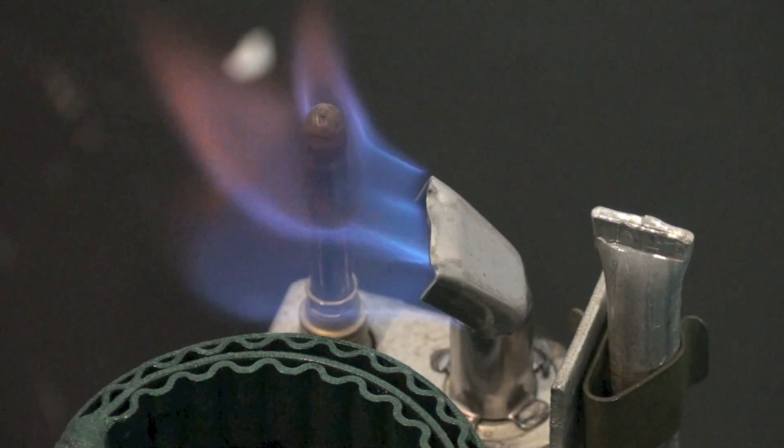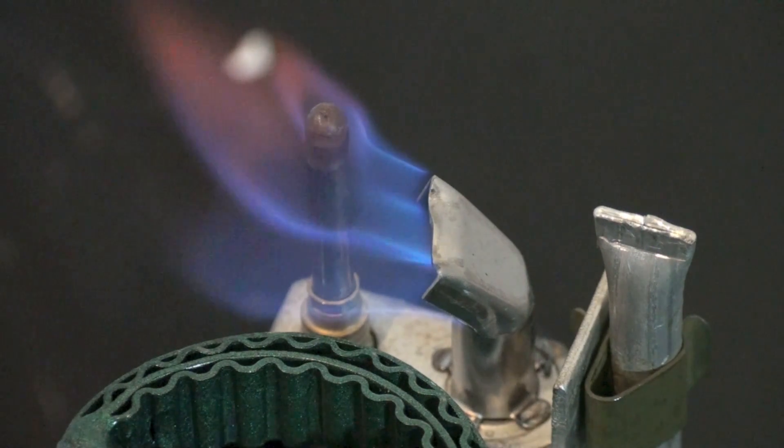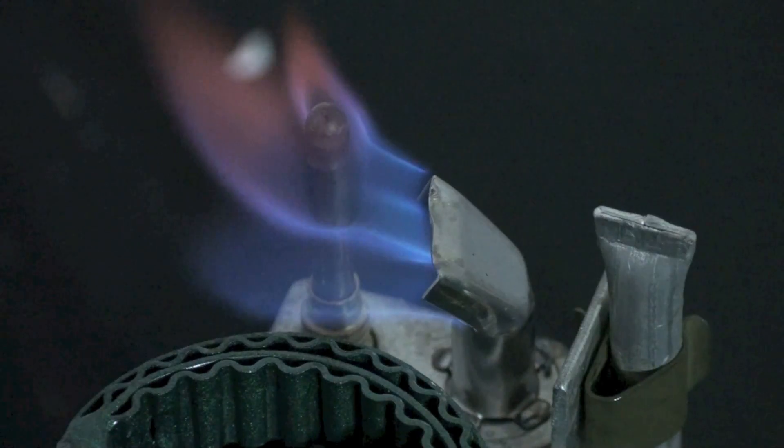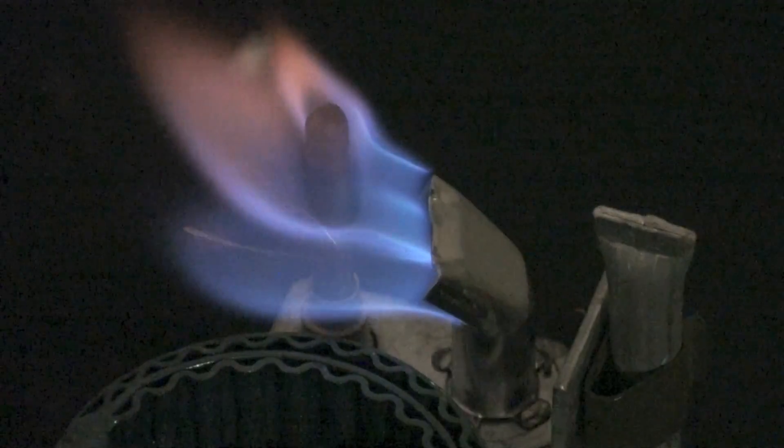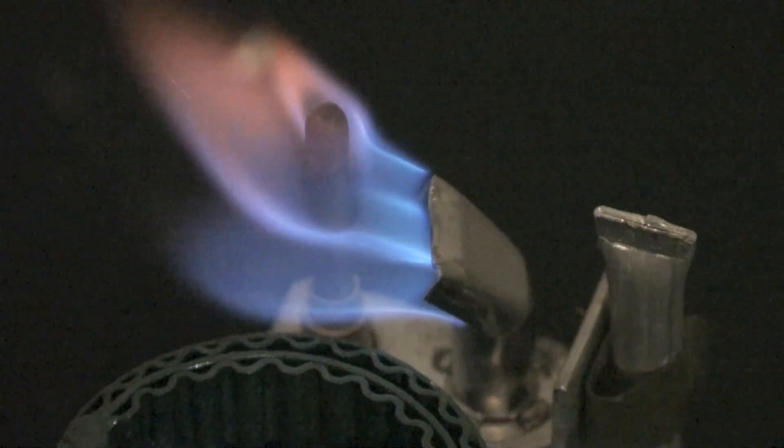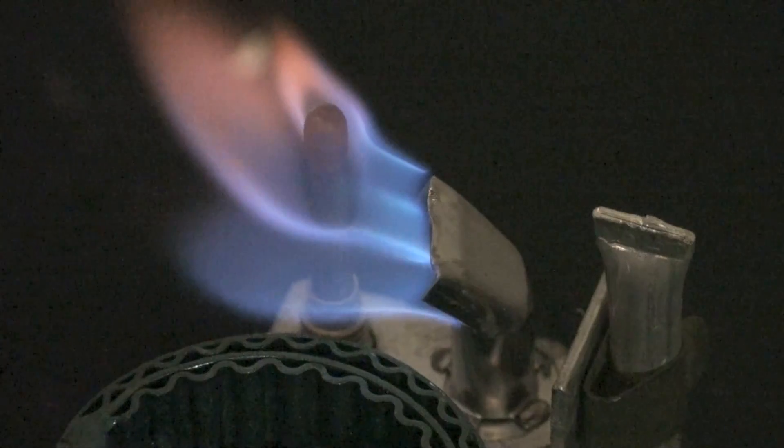Okay, this pilot is blue. It's supposed to be blue. It's going straight out. It should go straight out. Now, you may be able to see a little better there. It's playing on the thermocouple just about exactly the way it should.